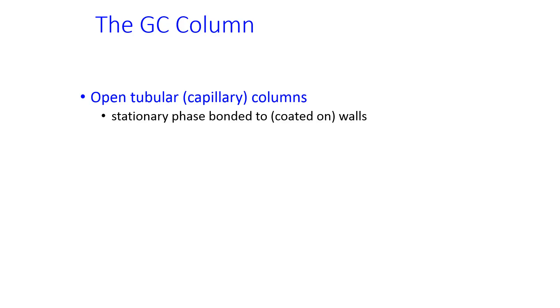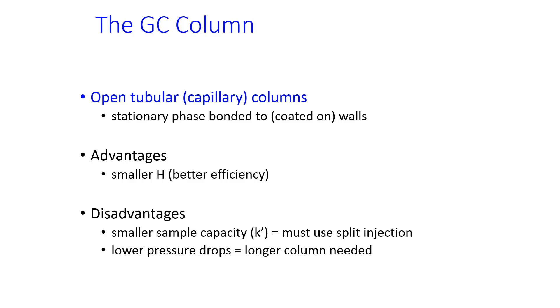As compared to a capillary column. In a capillary column, the stationary phase is coated onto the walls of the column instead of packed in. The advantages of this is that they're more efficient than a packed column, but they have a smaller sample capacity. So, open tubular columns almost always use split injection instead of direct injection. You also need a longer column because you can't have as big of a pressure difference between the beginning and the end of the column with this kind.